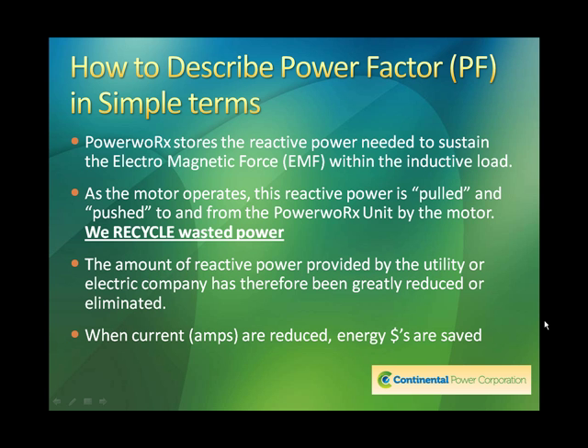To describe power factor in simple terms, the PowerwoRx stores the reactive power, the kVAR, needed to sustain the electromagnetic force, also known as EMF, within the inductive load. It provides the reactive current so we can magnetize the windings. As the motor operates, this reactive power is pulled and pushed to and from the PowerwoRx by the motor. So the capacitors in the PowerwoRx supply the motor with the reactive energy it needs. When the AC waveform starts going negative, the motor is giving up that current, and it's at the exact time that the capacitor needs it. So there's this pushing and pulling between capacitors and the motors, and ultimately, if you want to think of it this way, we recycle the wasted power, and therefore it's not needed to be supplied by the utility.